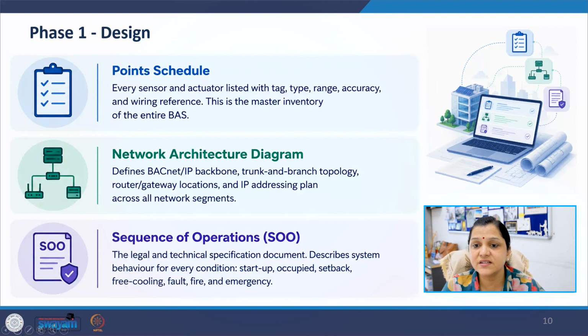The design phase creates the technical foundation of the entire building automation project. One major document is the points schedule. This is a complete inventory of all sensors, actuators, controllers, and field devices. It includes status, ranges, accuracy, and wiring references. The next important document is the network architecture diagram. This diagram defines communication topology, BACnet IP structure, router locations, and IP addresses. Finally, the sequence of operations defines system behavior under all operating conditions.